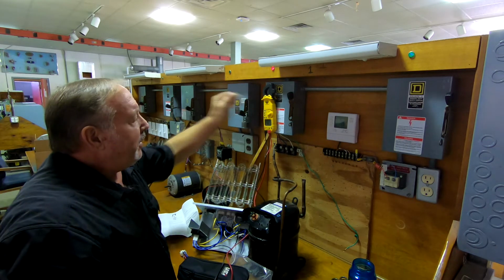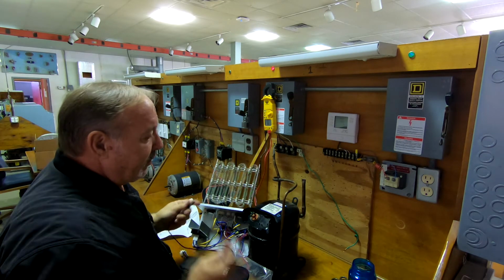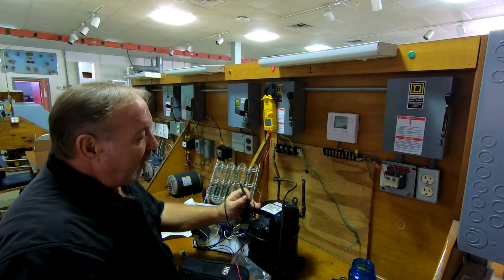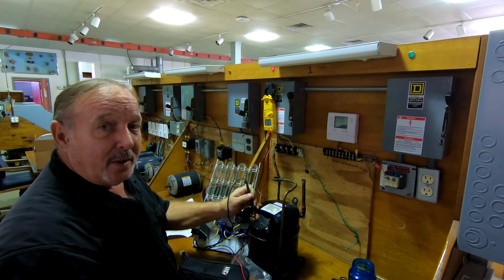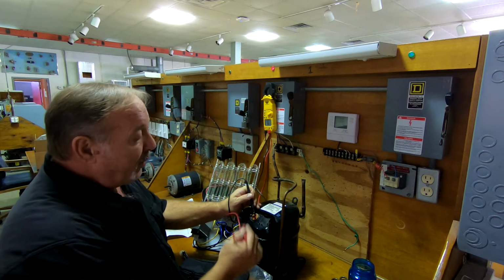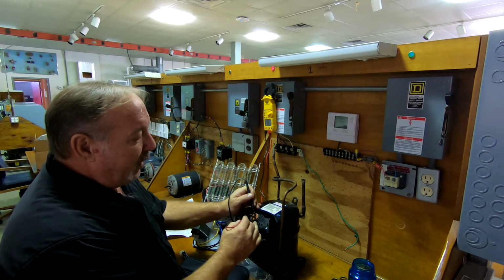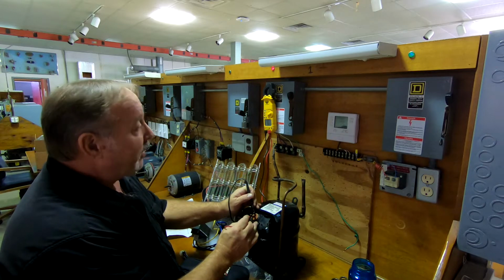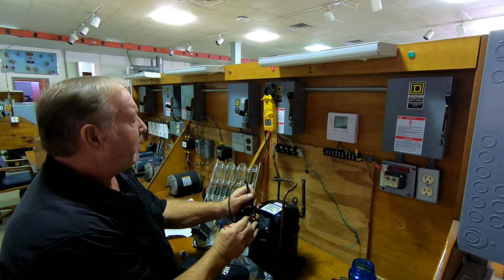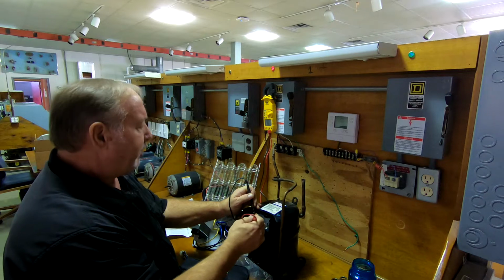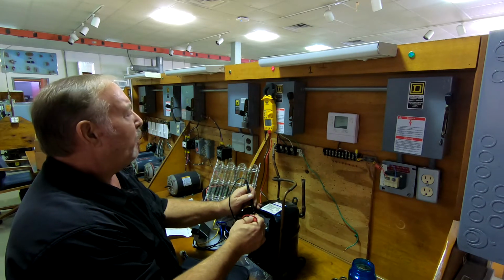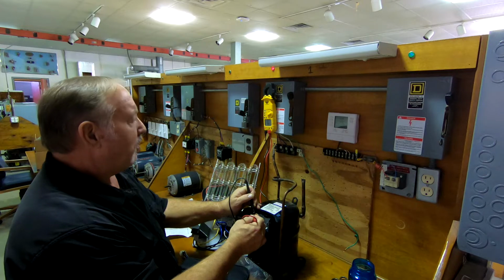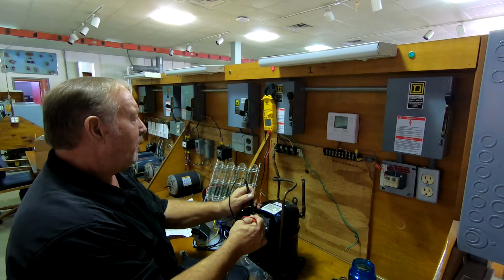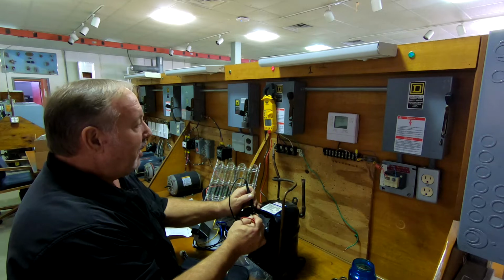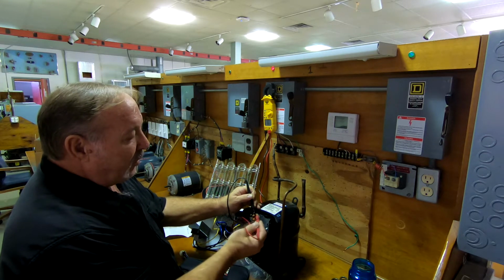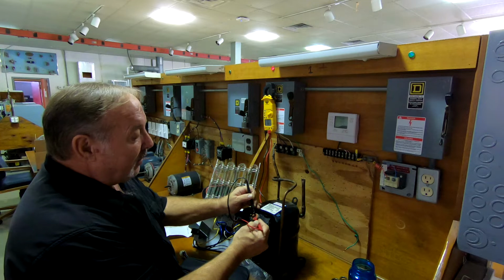The next reading up here is for ohms. If you want to measure the windings of a compressor, remember they're additive. When we go between common and run, that's going to give us one value. In this case, it's telling me that I have 4.3, 4.2 ohms. Actually, 4.1, 4.2. Now I'm going to switch over to the second terminal here.